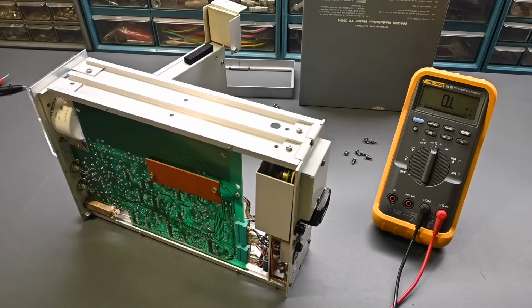Now I need to recalibrate the instrument on that range, and I might touch up the other range as well, just to dial things in exactly, because that potentiometer, you know, it's midpoint, but that's not really where it's supposed to be for the actual calibration. So let me reconnect this over to the RF signal generator, and let's make the calibration on that range, make it nice and accurate.